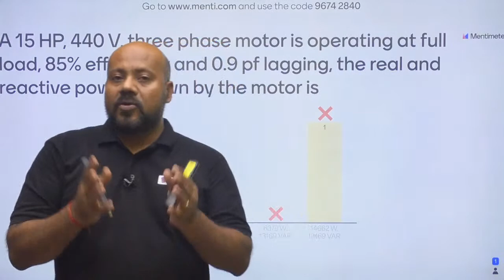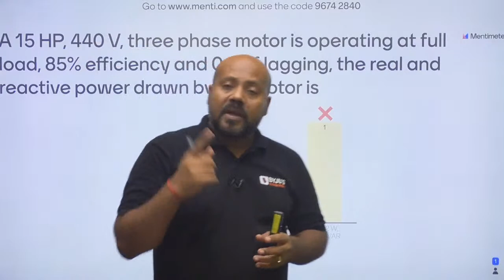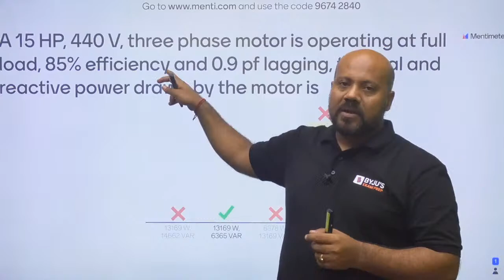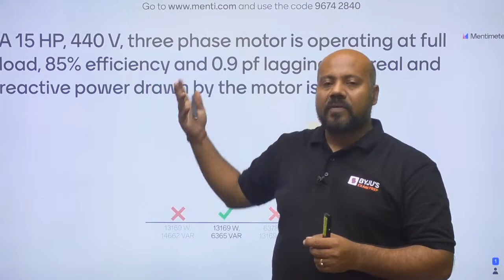15 horsepower multiplied by 746, because 1 horsepower is equivalent to 746 watts. So you will be getting the total electrical equivalent power output for the motor. Use the efficiency relation. Efficiency is also given, 85%. What is efficiency? P output upon P input. P output you know, efficiency you know, 85%, you can find the P input. It means the real power taken by the motor you can directly solve now.